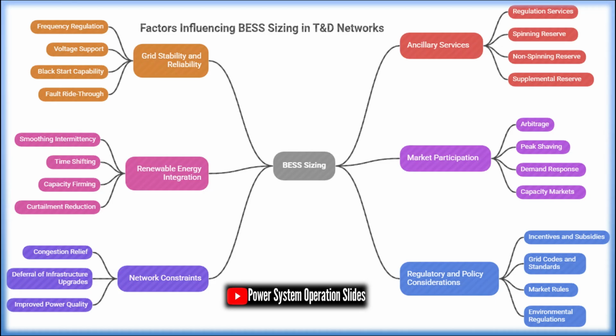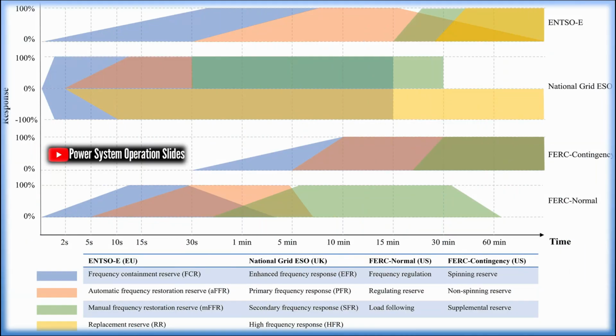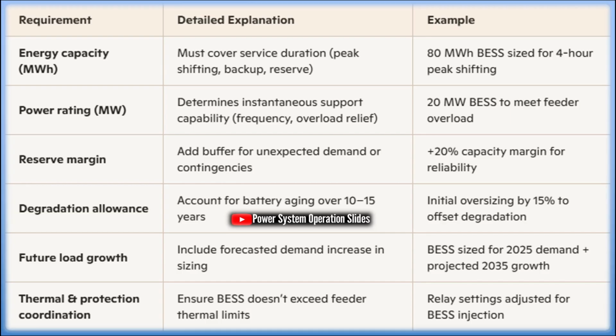These revised models now use more aggressive degradation assumptions and incorporate operational strategies such as limiting the SOC operating window and reducing cycle depth during periods of high temperature stress. The California experience demonstrates that poor degradation modeling can lead to both financial and operational failure. Projects that appear economically viable based on simplified sizing models may fail to meet performance targets and may require premature repowering or replacement. This lesson has influenced BESS sizing practices worldwide, with operators increasingly requiring detailed degradation models that account for operating conditions, cycle patterns, and environmental factors.